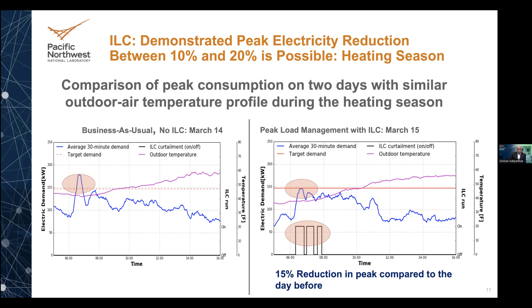Next day on the right, when we ran ILC to manage the building peak, we set a target of 150, the red horizontal line, and the peak on that day never exceeds the target of 150, which was also set around 7 a.m. Note that one or more of the heat pumps were curtailed at the bottom to manage that load change. Compared to the first day, the peak reduction is almost 15 or 20%.